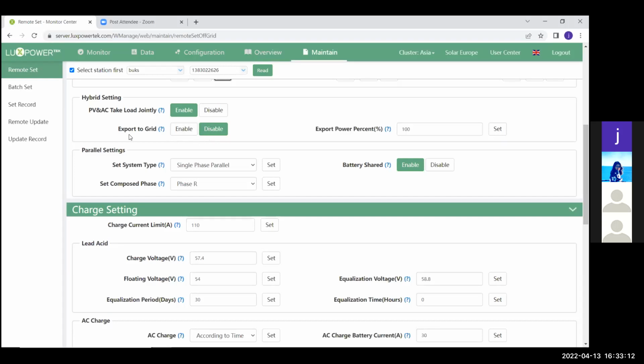If you enable the export to grid, all available PV power that can't be used for charging the batteries or the house loads will be exported to the grid, and you can put the percentage here. So if you see you only need 2-3 kilowatts a day to be exported, you can play with this percentage up and down until you've met the amount that you would like your system to export, so that you can roughly balance out your meter with the usage, so you don't go into the negative on your meter.